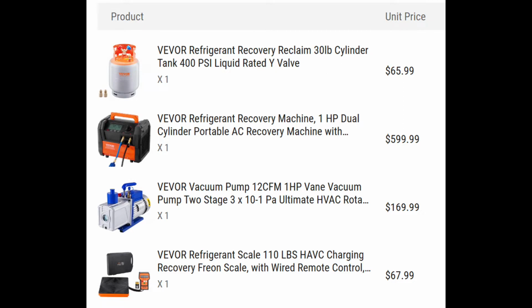This video is not a step-by-step in-depth video for this process. It simply is to give you a high-level overview of what it takes to replace a split HVAC system. So you'll need a recovery tank to recover the old refrigerant out of the old system, and a recovery machine. You'll need a vacuum pump to pull a vacuum on the new line set or the old line set.